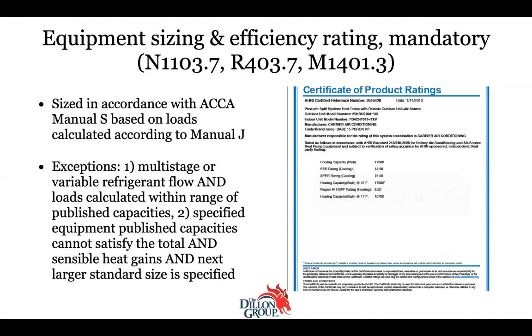The equipment sizing and efficiency rating, this is another mandatory requirement, and it says it has to be sized in accordance with ACCA Manual S, on loads that are calculated according to Manual J. Under the 2018 code, there's two exceptions. If they're using a multi-stage or variable refrigerant flow and the loads are calculated within the range of published capacity, that's one exception. The other one is if the specified equipment published capacities cannot satisfy the total and sensible heat gains and the next larger standard size is specified. Not two sizes, not three sizes up, the next larger standard size.